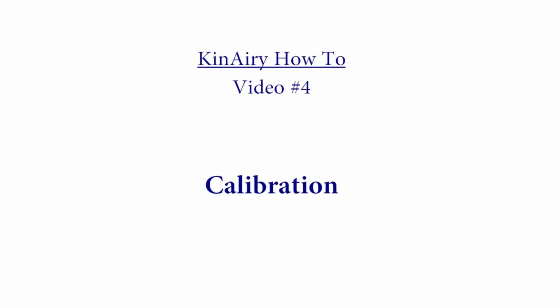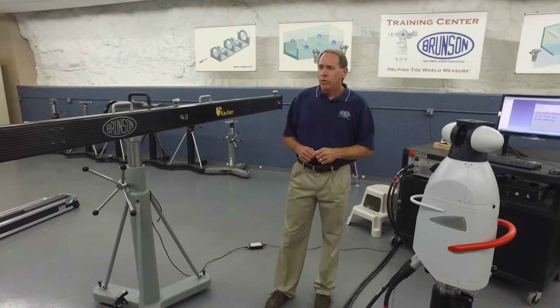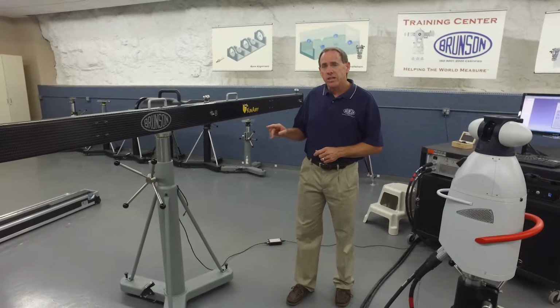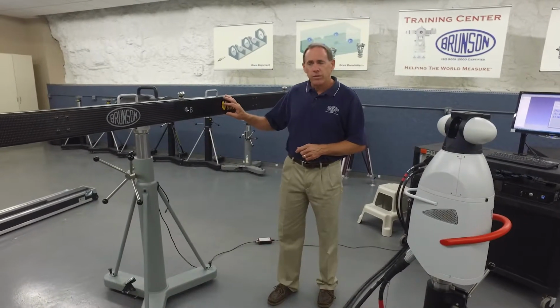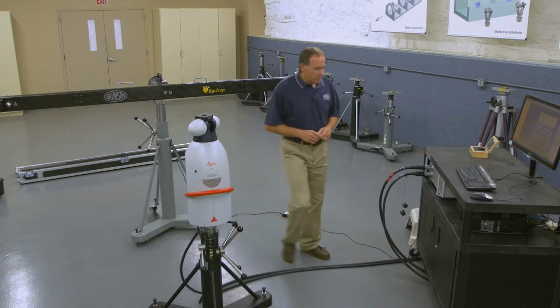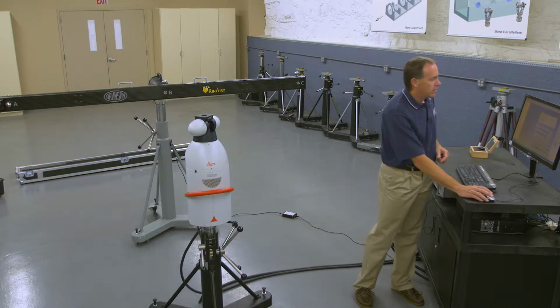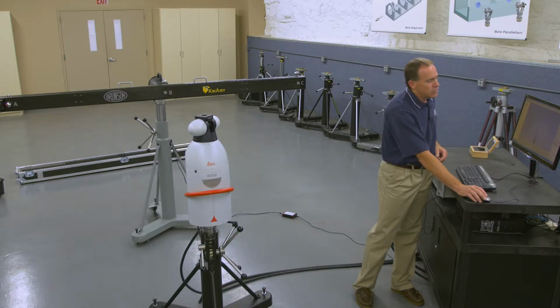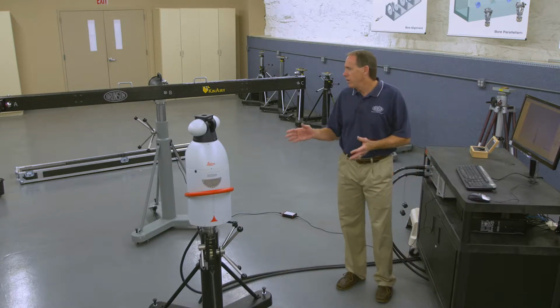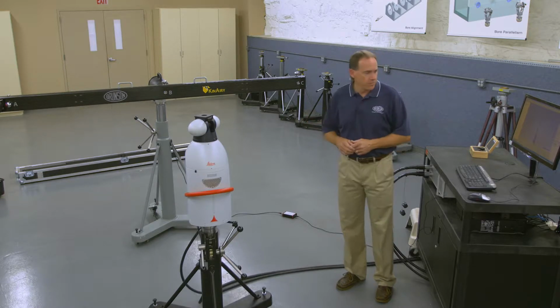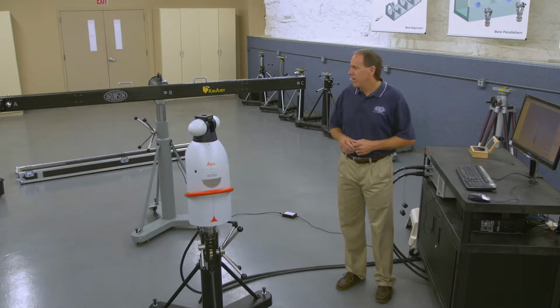So now that the ranging component has been isolated and bucked into the bar, we're ready to begin the calibration process to value the length of the bar. So to do that, I'm going to close this window out, and we'll go back to IFM mode. This tracker does have that capability, so we're going to use that to help value the bar. And we're ready to begin taking our calibration measurements.